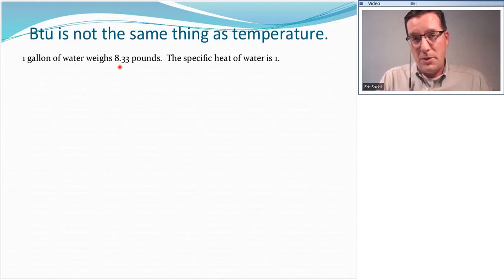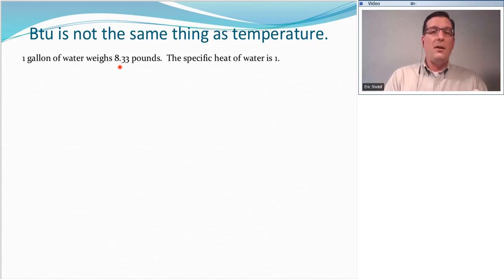Why is this important to remember? It's because of this. We always measure water flow and water quantity in gallons, in volume. We always measure heat transfer in pounds, BTUs per pound. We don't do BTU per gallon, we do BTU per pound. So we always have to convert gallons into weight if we want to measure BTU transfer. So one gallon of water weighs 8.33 pounds.